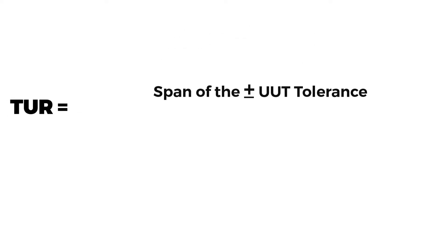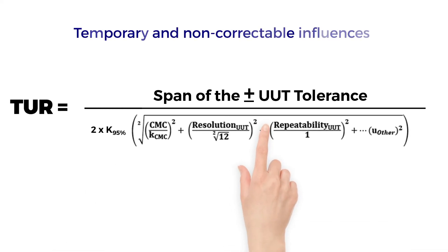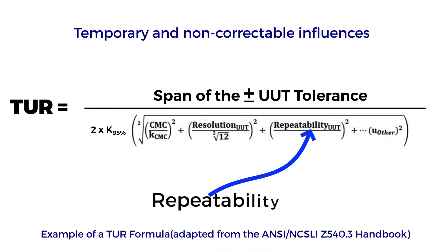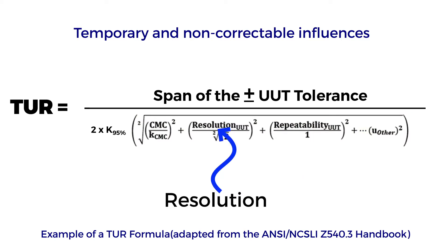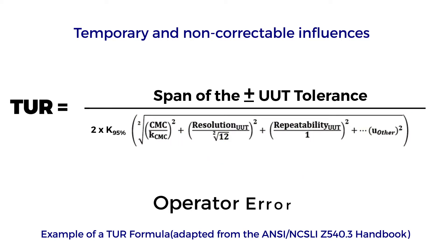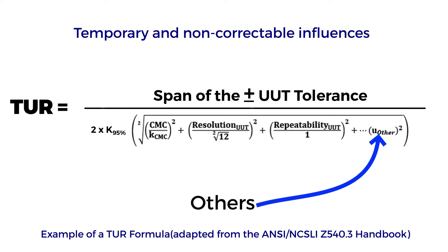The formula for TUR consists of the span of the tolerance in the numerator. The denominator includes temporary and non-correctable influences incurred during the calibration, such as repeatability, resolution, error in the measurement source, operator error, error in correction factors, environmental influences, and others.